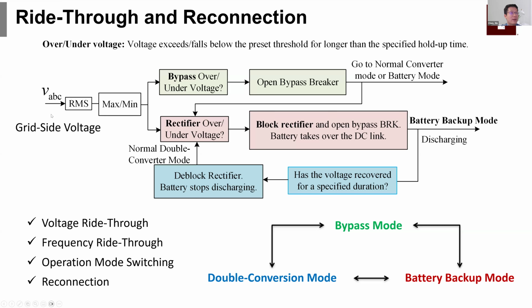So it depends on the grid side voltage. We have all those flow charts to control the mode switching so that our system can switch among the bypass, double conversion, and battery backup mode depending on the grid side voltage. And in our model, we can achieve the voltage ride-through. We have embedded the voltage ride-through mechanism, frequency ride-through mechanism, also these three operation mode switching as well as the reconnection. If the grid side voltage is recovered to a good condition, we can reconnect the data center to the grid.